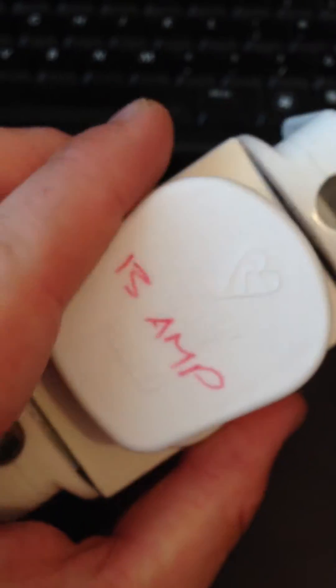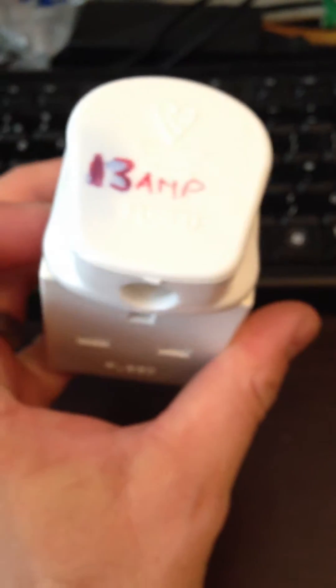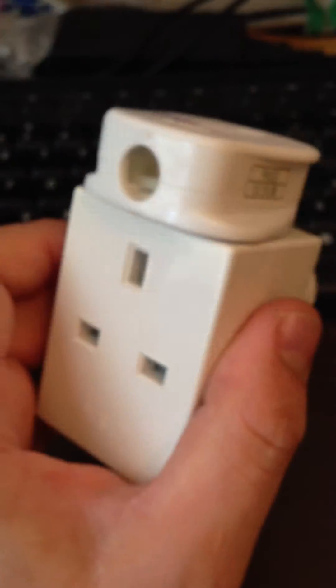If we've got a 13 amp plug, a 13 amp plug and a 5 amp plug plugged into it, it's overloaded. Which means, I'll just disconnect these, the socket adapter should only have one 13 amp plug connected to it.